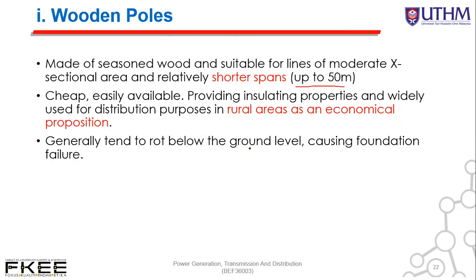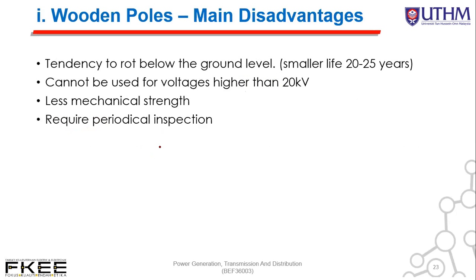Generally they tend to rot below the ground level, causing foundation failure, because wood is not long lasting. Dalam bahasa Melayunya dia senang rosak, kena makan dengan anak-anak dan sebagainya. So jadi dia boleh mudah untuk terbenam, tenggelam ke dalam tanah, yang akan menyebabkan foundation failure. So the wooden pole also has disadvantages: tendency to rot below the ground level, so a smaller lifespan of only 20 to 25 years. It cannot be used for voltage higher than 20 kV. Less mechanical strength and requires periodical inspection. Kena buat inspection banyak kali untuk pastikan keadaan kayu dia rosak ataupun masih okey.